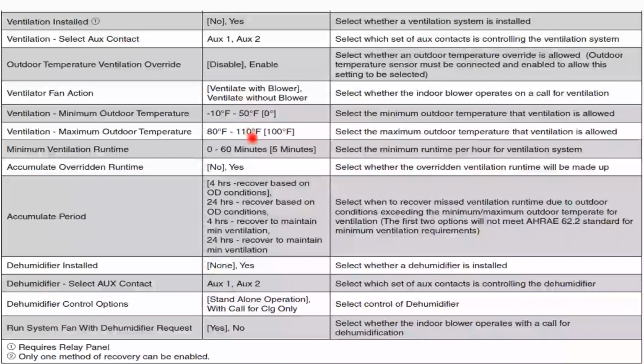We can actually change this. So if those get tricky, if we have a manual air damper and it's stuck open and it's 20 degrees out and we're pulling in 20-degree air across that coil, mixing with the 70-degree room temp, and we're getting like 46-degree return air, we can shut that and make sure we're not pulling in 30-degree air by changing the settings. That way it uses the outdoor temperature sensor. If it's below 30, it will not do makeup air. So keep that in mind. There's a lot of options in the accessory settings.